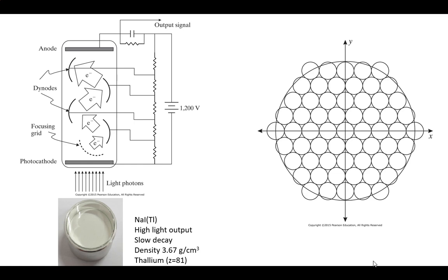The other thing is it's not very dense. Most of the more expensive, fancier ones that have really good decay rates and things like that that come in later are about twice this density. So these two deficiencies will make it completely unacceptable for PET. The first couple of systems they tried to do in PET, they tried to use this because it was like the standard.